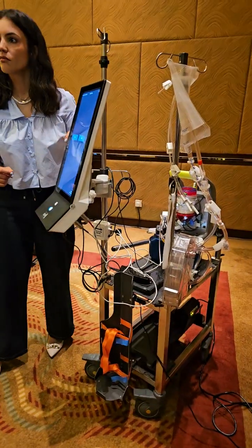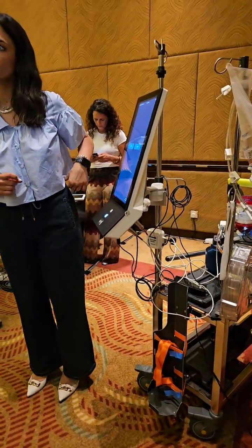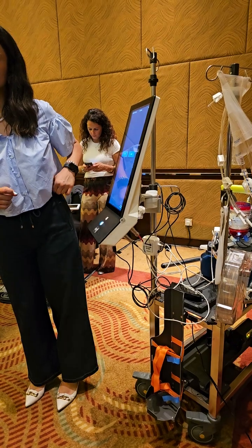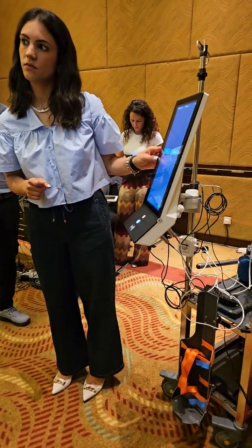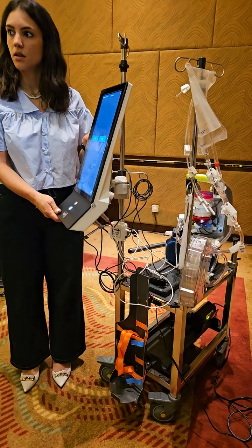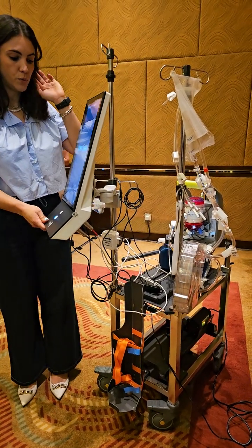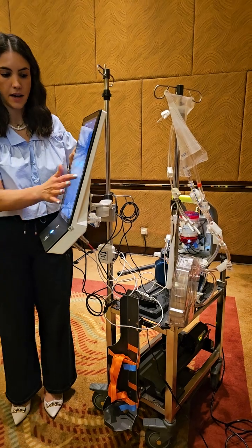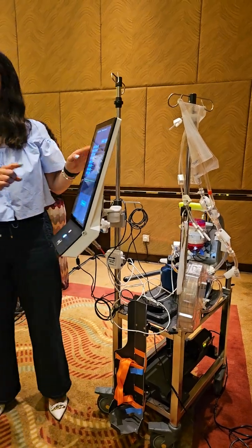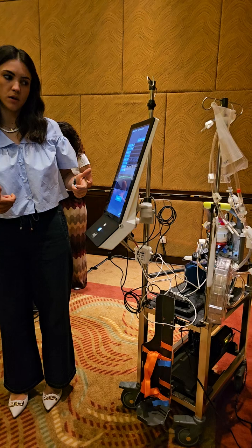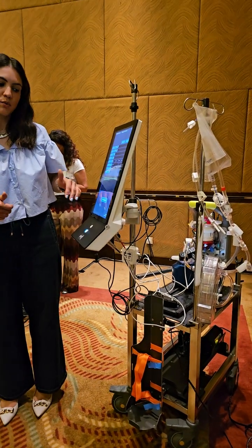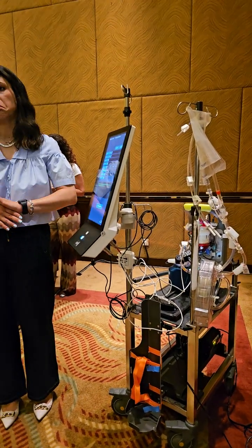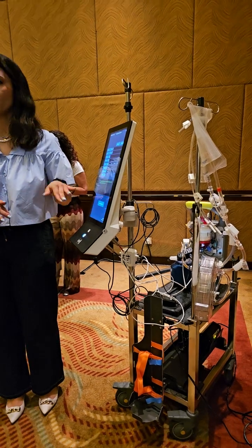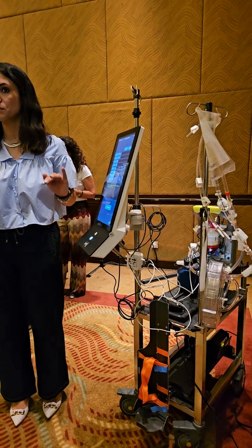Okay, can calibrate it through the machine, right? Through the monitors. You do the auto calibrations. Yes, using without cuvette, you have to pass a diagnostic phase. So once you switch the monitor on, you have a diagnostic phase which is mandatory, but is very fast. It requires only a few seconds to be performed.